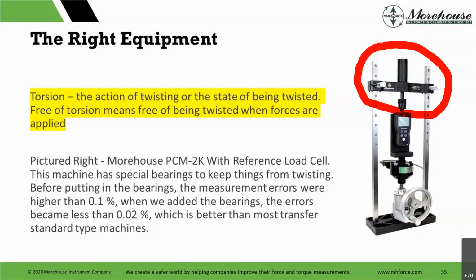So what we did is we designed this section here that I circled. We designed a mechanism, and those that want to see it can go online and pull down the PCM under products, PCM. You can see it's a mechanism with bearings, cylindricals, sphericals, everything else to lower the torsion. Right now, if we take 2 standards calibrated by dead weights, the torsion in this machine is going to be about 0.01%. We have not eliminated it, but we've made it really, really low. So for those using a transfer standard, something like this, it's an additional error component you have to deal with that's not found in dead weight. So take it for what it is. We've reduced it. That number of 0.01 is very, very low for a force machine.